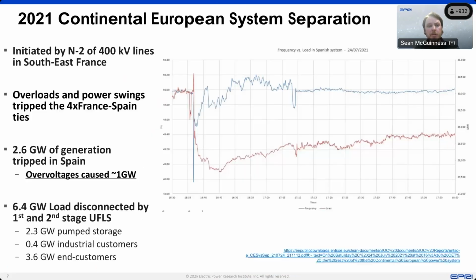There was in 2021 a pretty significant event. They're part of the continental European grid, which is about 500 gigawatt peak load across the entire continent. In 2021, there was a number of wildfires in the southeast of France. Smoke from some of them caused the tripping of a 400 kV line, and about 2 minutes later, the other line on the same circuit also tripped. It was carrying about 2.5 gigawatts of load prior to the event. When the initial line tripped, the operators were taking actions to de-risk and deload the system, but the second line tripped before those actions were completed.